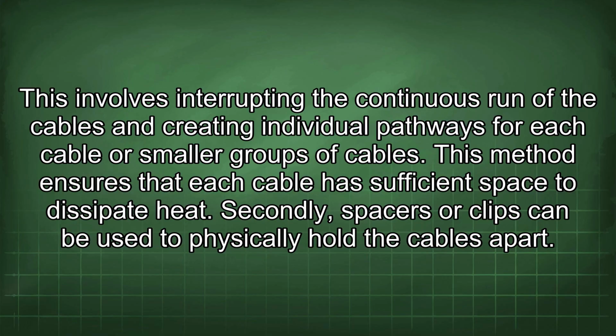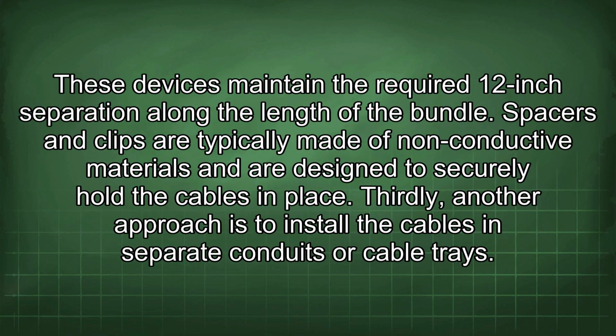Secondly, spacers or clips can be used to physically hold the cables apart. These devices maintain the required 12-inch separation along the length of the bundle. Spacers and clips are typically made of non-conductive materials and are designed to securely hold the cables in place.